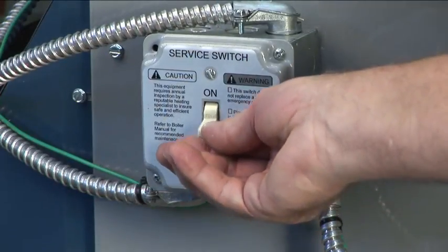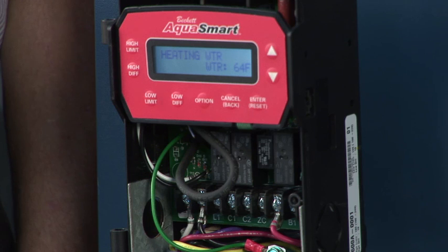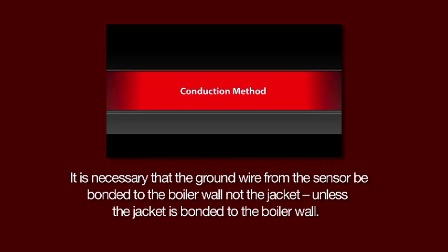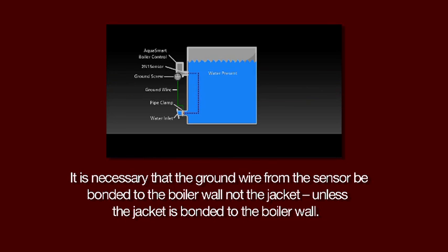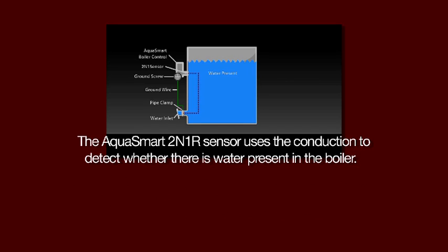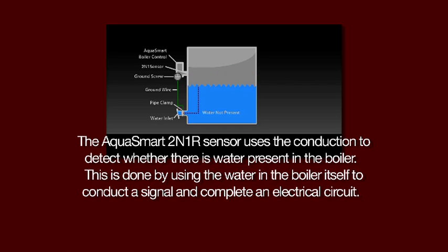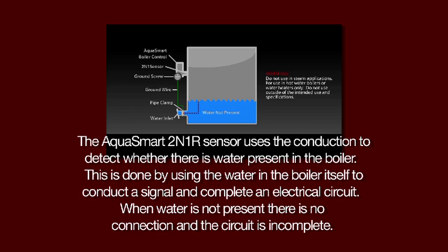Turn on the power to the appliance and observe one call for heat cycle, making sure that it shuts off at the set temperature. It's necessary that the ground wire from the sensor be bonded to the boiler wall, not the jacket, unless the jacket is bonded to the boiler wall. The AquaSmart 2N1R sensor uses conduction to detect whether there is water present in the boiler. This is done by using the water in the boiler itself to conduct a signal and complete an electrical circuit. When water is not present, there is no connection, and the circuit is incomplete.